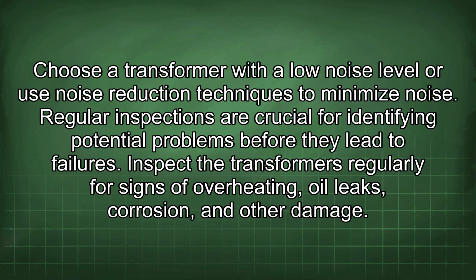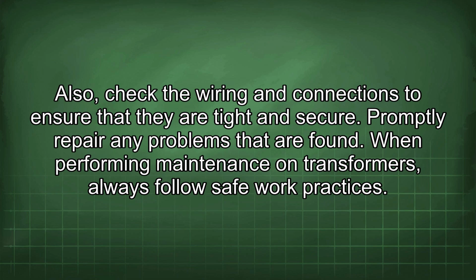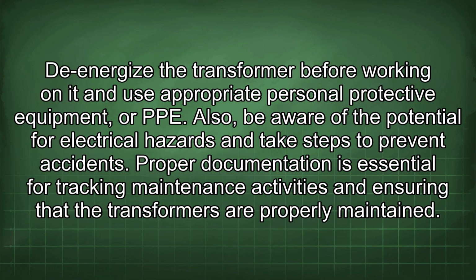Regular inspections are crucial for identifying potential problems before they lead to failures. Inspect the transformers regularly for signs of overheating, oil leaks, corrosion, and other damage. Also, check the wiring and connections to ensure that they're tight and secure. Promptly repair any problems that are found. When performing maintenance on transformers, always follow safe work practices. De-energize the transformer before working on it and use appropriate personal protective equipment, or PPE. Also, be aware of the potential for electrical hazards and take steps to prevent accidents.